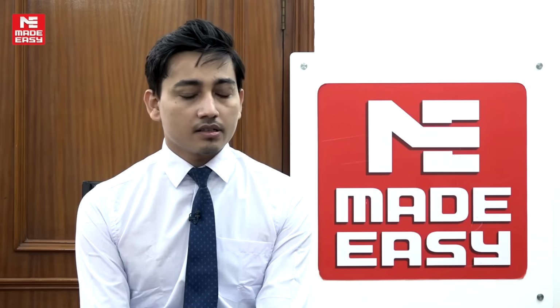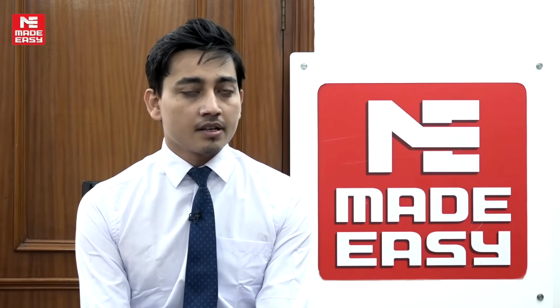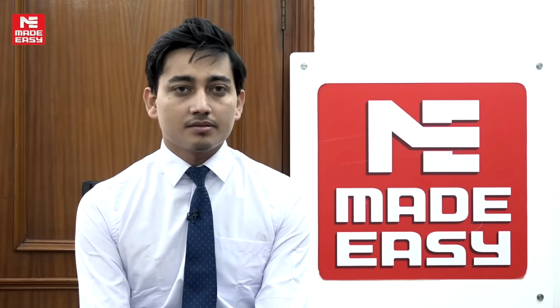Yes, sir. I'll talk about the last challenge that I faced when I was in transmission, 132/33 kV, Jhansi. There was a 400 MVA transformer which got burnt out completely. The tank was completely cracked, and the NIFPS mechanism, the nitrogen injected fire protection scheme, also worked. I was involved with the chief engineer, and we did all the tests like SFRA, sweep frequency response analysis of that transformer, and oil testing, oil breakdown test. We found that the main reason for the fault was oil leakage from the breather, due to which the Y-phase breather was completely burnt out, which led to total current coming on the tank. Then the tank cracked, and all protection schemes worked.